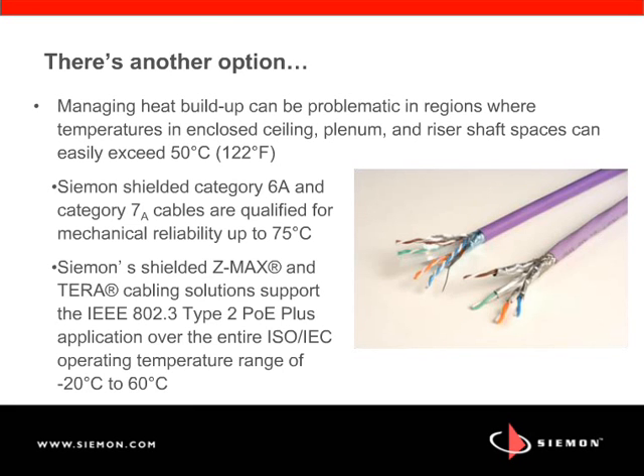There are cables, such as the Siemon shielded Category 6A and 7A product line, that are qualified for mechanical reliability to higher temperatures. Our systems are qualified for mechanical reliability up to 75 degrees C, which is 167 degrees Fahrenheit. And these cables are going to exhibit superior heat dissipation, and as a result can be installed in environments up to the maximum TIA operating range of 60 degrees C. And they won't experience mechanical degradation caused by the combined effects of high temperature environments and heat buildup within the cables.